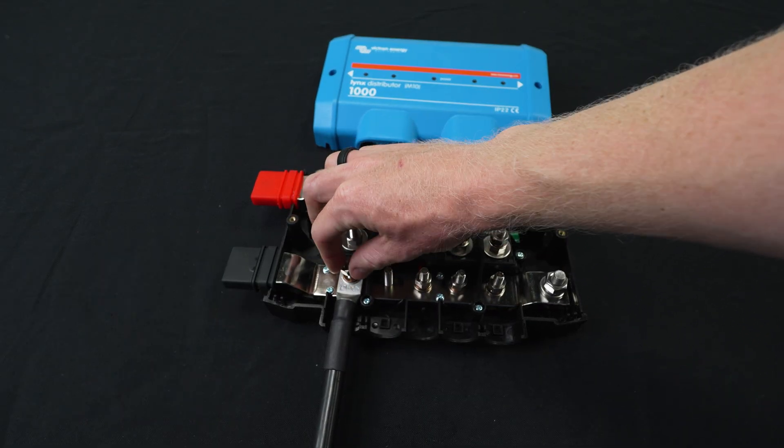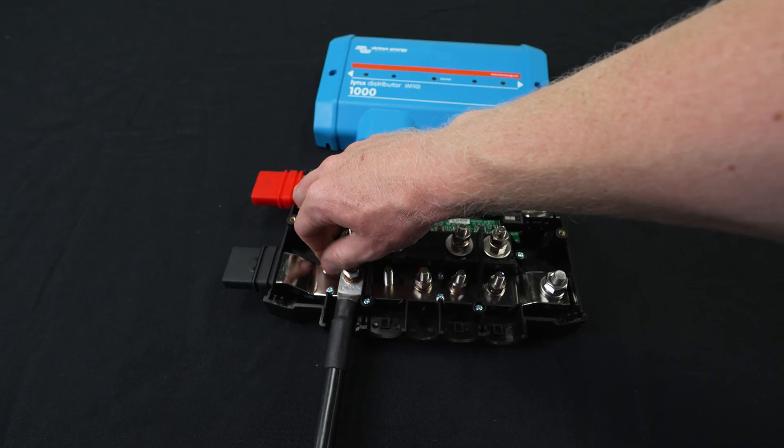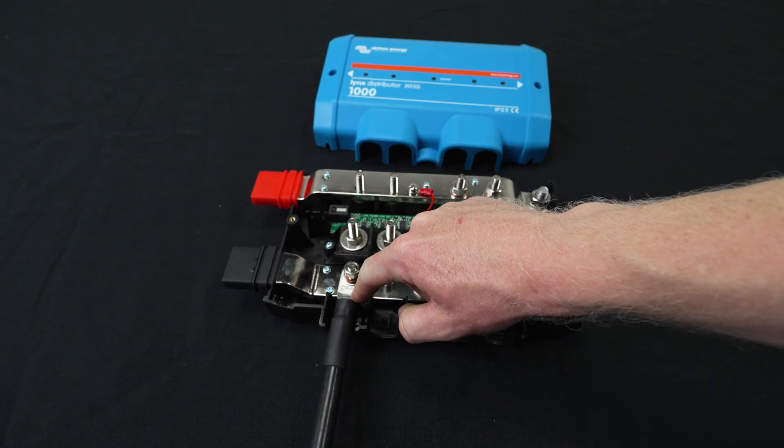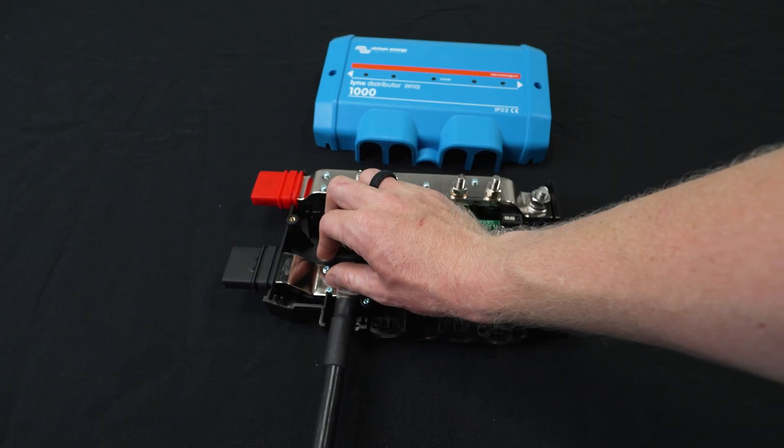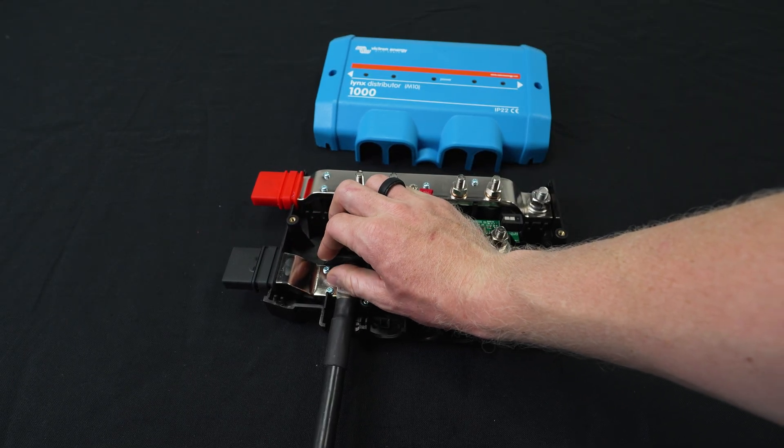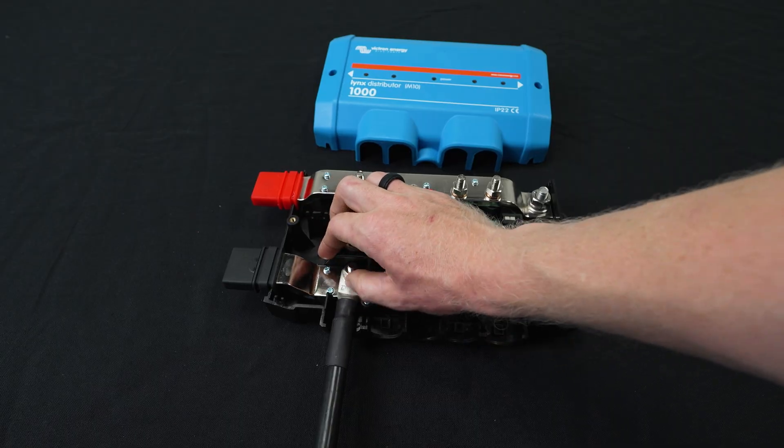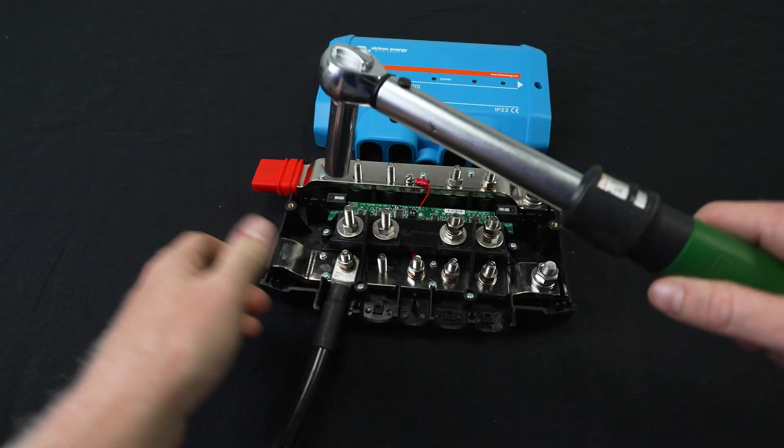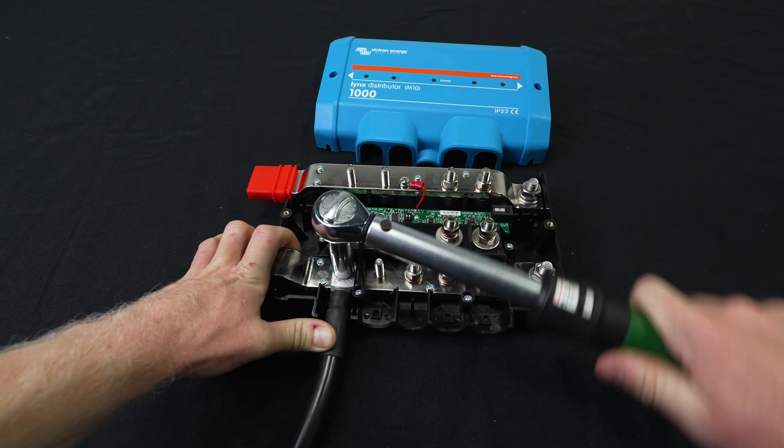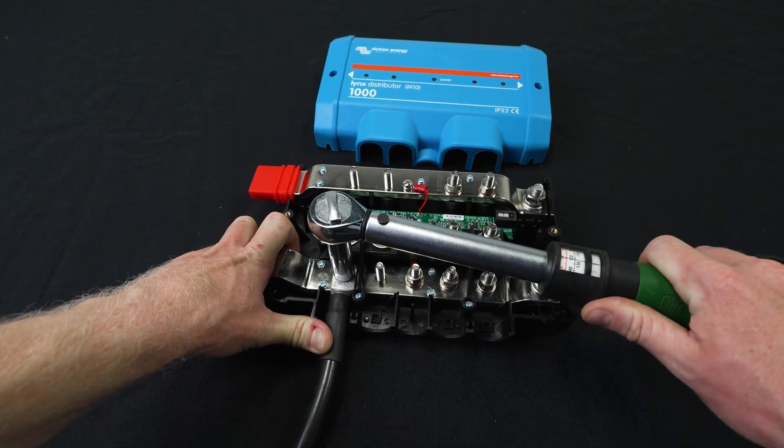So you never want anything to go between the current carrying conductor, which is the lug, and the bus bar. So that's why we put the lug down first, attach it directly to the bus bar. Nothing in between those two causing extra resistance, extra heat. 14 newton meters. Perfect.